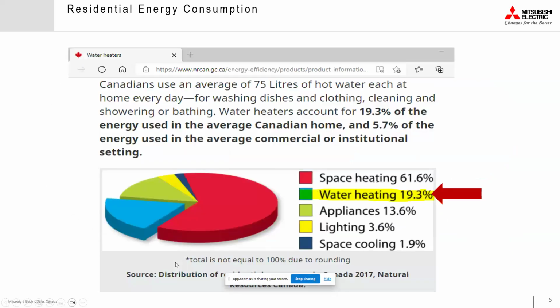Let's talk about the water, especially in the residential building, what the heating consumption or energy consumption is, especially for heating the water. From a Natural Resources Canada recent study in 2013, the average Canadian is consuming 75 liters of hot water each day, and obviously that goes to your clothing, cleaning, dishwashing, bathing, and all the needs. But overall, it's 20% of energy consumed just for heating the water for your daily usage. So that's the amount of energy we are consuming continuously. And it's not like heating or cooling, which is seasonal. That is something you need all around the year. That's why it's a huge amount of energy.